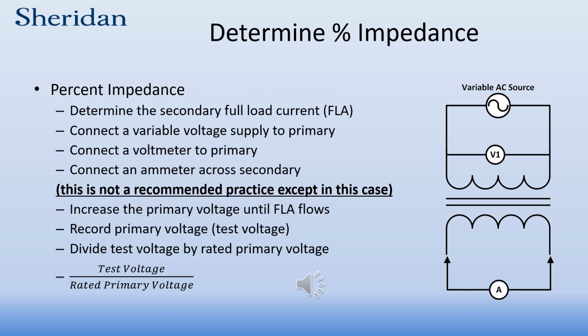Okay, so the impedance test is done by, first of all, determining the secondary full load current, FLA. You connect a variable voltage supply to the primary and connect a voltmeter across that to determine the voltage which you're applying. You put an ammeter across the secondary, or short the secondary. An ammeter really is a short. It has very little resistance to the flow of current. Or put in a short and use a clamp-on ammeter.